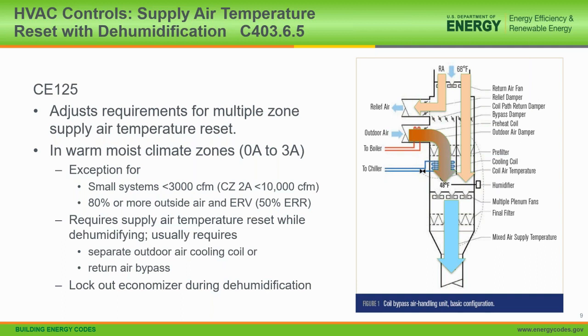One way is to add a separate cooling coil for the outside air. The other way is to provide a bypass of return air so the outside air is getting the primary cooling and dehumidification, and then the warmer return air is mixing in.